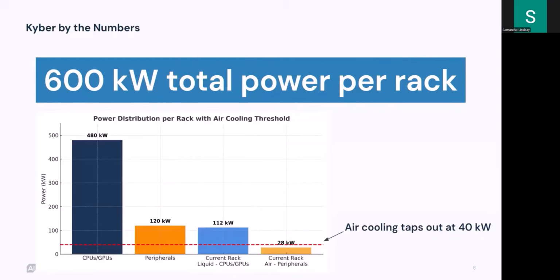But now if we move to these next generation systems, 600 kilowatts per rack, you do the math, take 80% off the top, you're still left with 120 kilowatts of heat that you need to remove from the system. That is as big as the biggest racks we're deploying today, and those racks already use liquid cooling, well above what you can reasonably cool with air at say 40 kilowatts. So there's basically no choice. There's going to be a requirement to put more of the heat load into the liquid cooling loop as we move to these very high power racks.